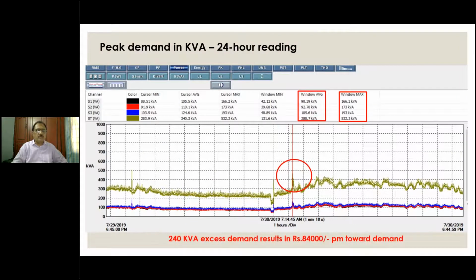Right, another window, same 24-hour measurement. We are looking at the demand. See, if you look at the demand, the average demand was only 288.7, because we saw average power was also 285 or something like that. The power factor was 0.982. But then there is a peak demand which is captured as Windows maximum, which is 532 kVA. So for a 288 average kVA used, they are paying 532.3 kVA.